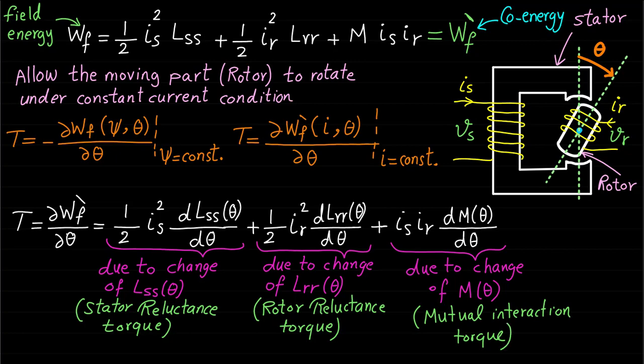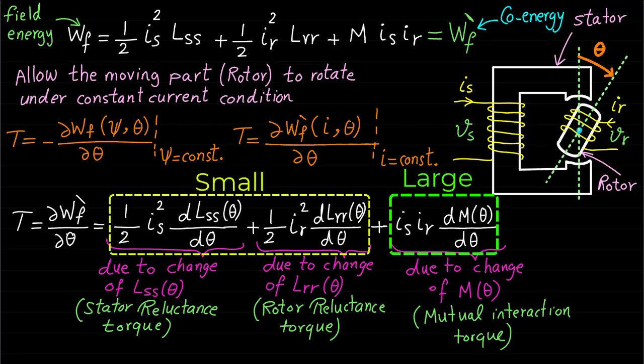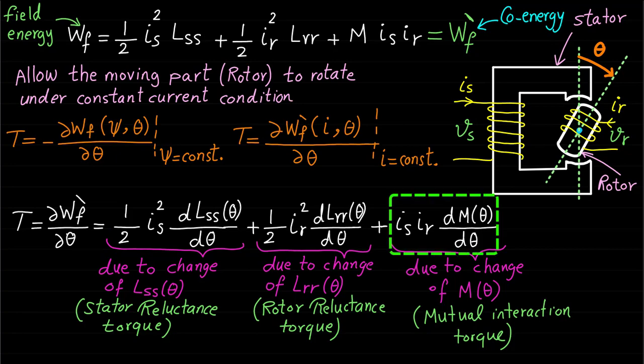This mutual inductance torque component can also be called the primary or main torque. Usually, the main torque or mutual interaction torque is larger than the reluctance torque components. The direction of the two reluctance torque components depends on the change of the self-inductances only and is independent of current direction because the current is squared. The direction of the mutual torque component depends on the change of mutual inductance and on the direction of both stator and rotor currents — it can be negative if Is and Ir have different signs, and positive if they have the same sign.